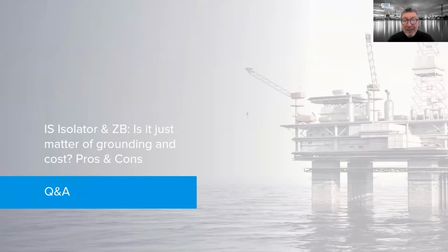We also have a question that says, an RTD certified as Ex c, can it be connected to an IS circuit? Yeah, you could. If you go back on the slide, an RTD is considered to be a simple device. And actually, here's an interesting question that has come up, and this is a little bit unique. With a lot of Ex equipment, for a thermocouple, you might get a thermocouple head in a small Ex d housing, and somebody will buy that thermocouple head from a manufacturer that makes Ex d housings. It'll have a U certificate at the end of it, meaning that it's only a component.